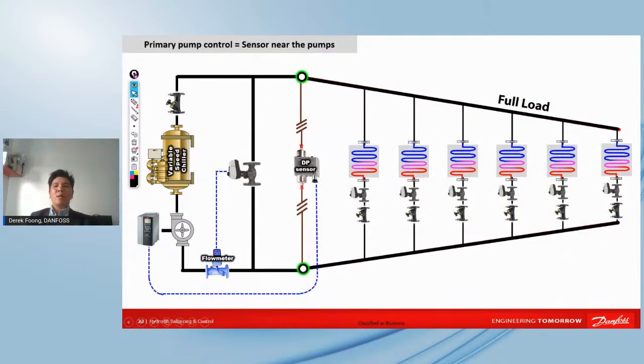What we saw just now, I would say 50% of the sites still have fixed speed pumps. And sometimes even if they install variable speed drives, when we go to the site and look at the system, it's running at maybe about 45 hertz, because no one really knows what the differential pressure set point for the pumps is. So it's a lot about trial and error. When we ask the end users how they operate, they'll just put the fixed speed a bit lower and then fix it there. So they try not to go into a very complicated system.